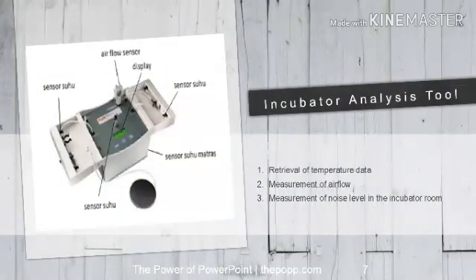After the electrical test, the baby incubator is then calibrated using a tool called an incubator analyzer. One, collection of temperature data. Data collection is used to measure the incubator space. This is important because if the base is too hot, it can blister the baby's skin. Two, measurement of airflow. Measurement of airflow is done because in the incubator room there must be air circulation. Three, measurement of noise level in the incubator room. If the value exceeds the threshold, it is feared that it will damage the baby's hearing system and of course makes the baby uncomfortable.